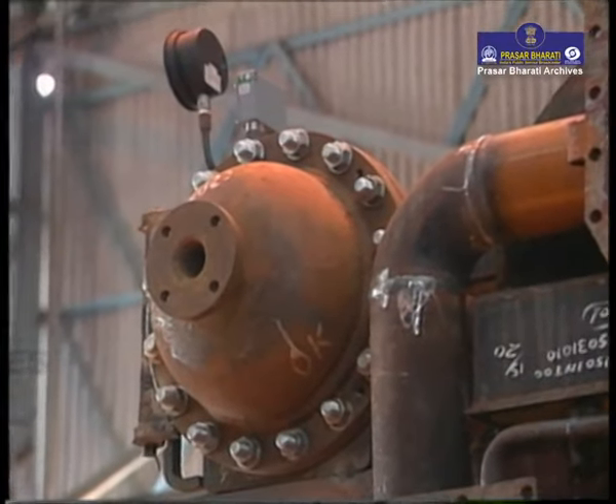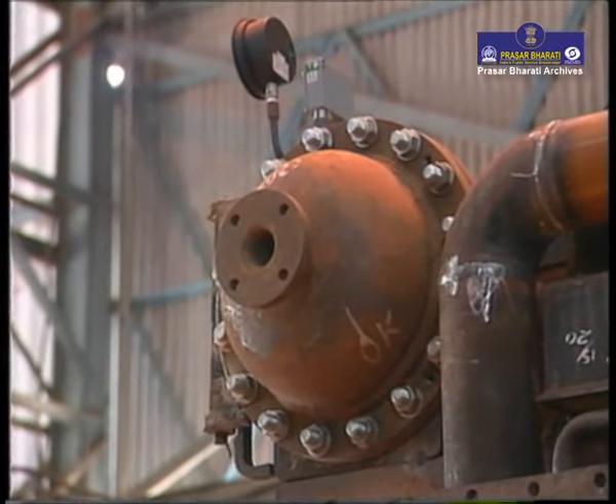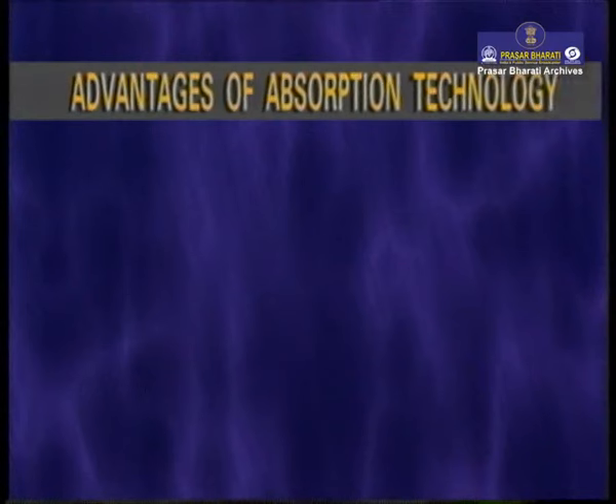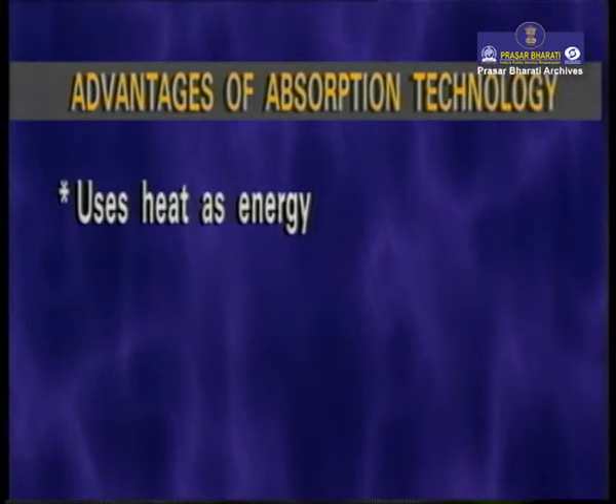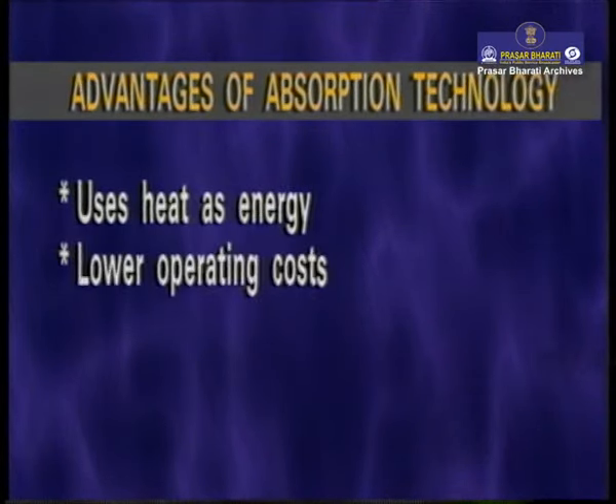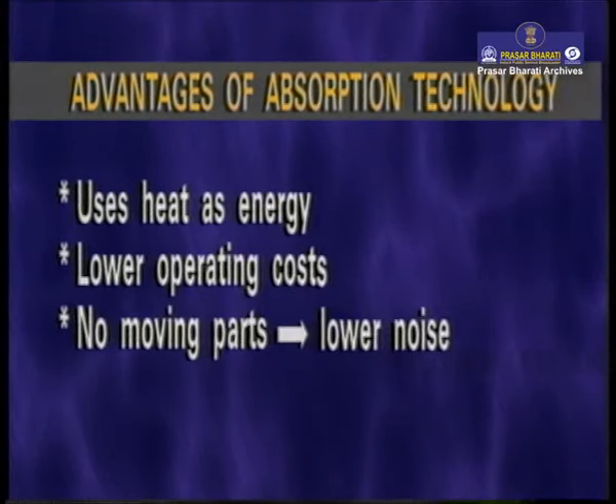The advantages of vapor absorption machines are many. Compressors are electricity guzzlers, while absorption chillers use heat as energy. This single factor vastly reduces operating costs. Further, since there are no moving parts involved in the absorption chillers, they are noiseless and require lesser maintenance.